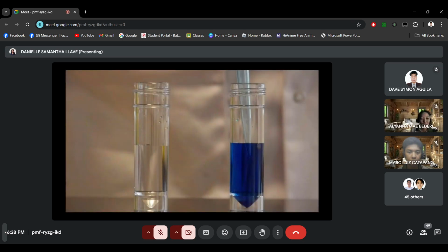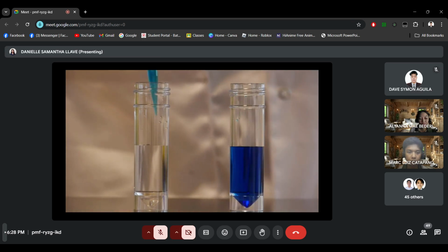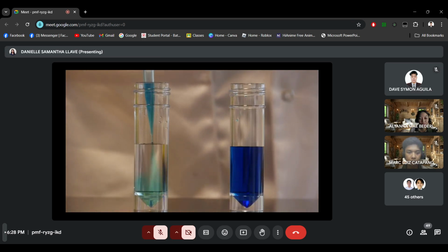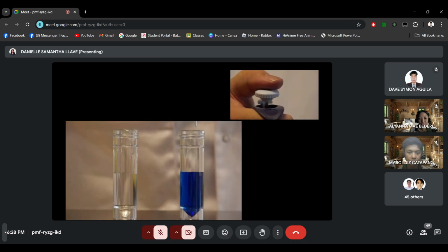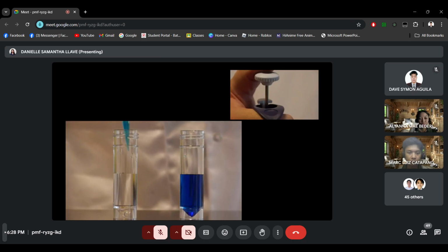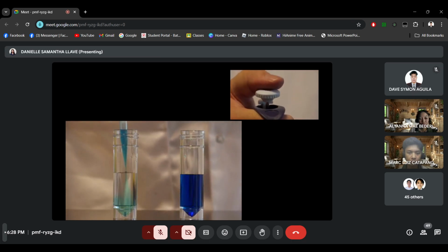Here we can see the liquid being taken up into the pipette tip, transferred over, pipette plunger is pushed down to the first stop, brief pause and then push through. Here you can see the actions together. Plunger comes up, liquid is taken in, we move over to the other container, push down to that first stop, pause briefly and then push through.